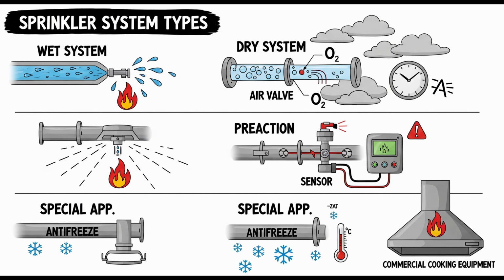But what about pendant or sidewall sprinklers? They hang down, seems like they'd trap water. They are prone to it. Pendant and sidewall sprinklers are only permitted under specific conditions. Such as? Either they must be installed on return bends, i.e. the sprinkler head itself, the return bend, and the short section of branch line piping connected to it are located in an area maintained at or above 40 degrees Fahrenheit. So you use a return bend to loop that little section of pipe back up into a warm space.